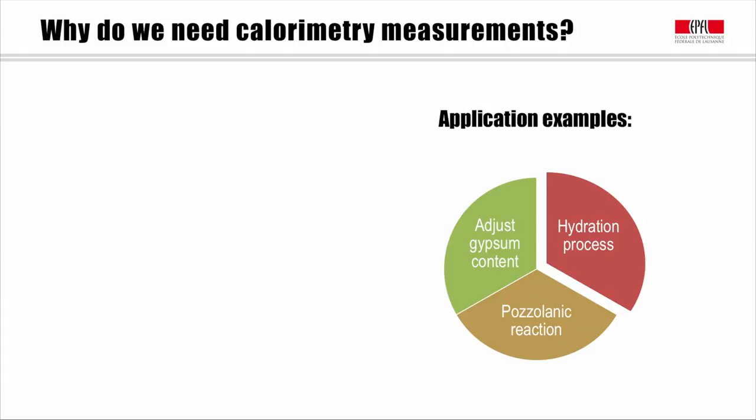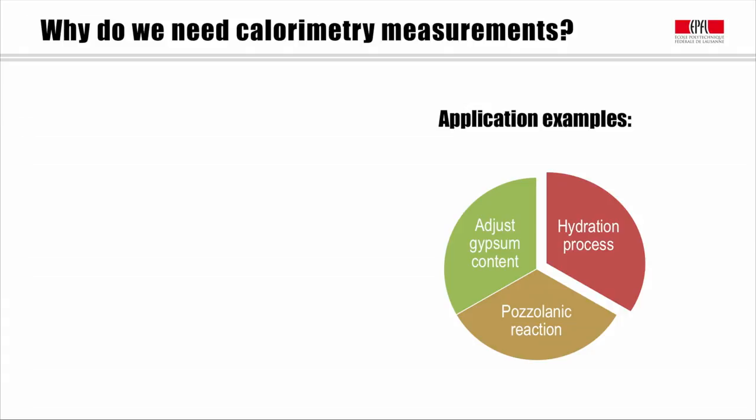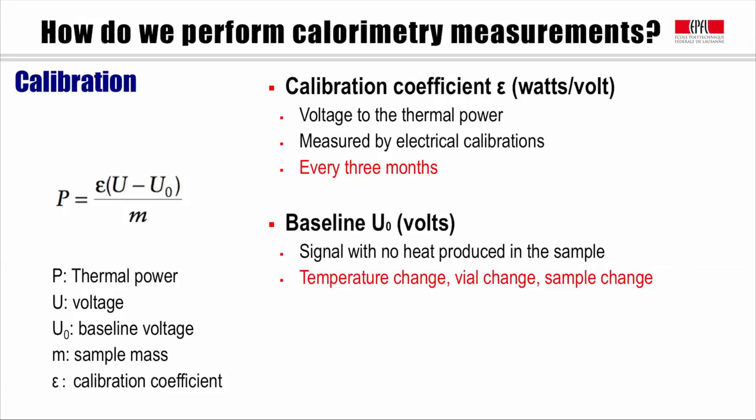Before we can perform a test, making sure that the instrument is in good condition is very important. This can be done by calibration. Isothermal calorimetry is actually a very stable instrument, but proper calibration will help to significantly reduce noise.